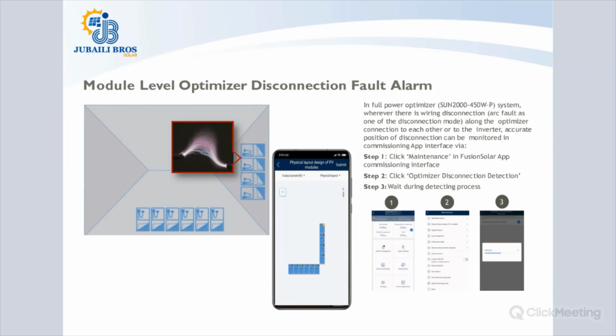Now, it will not be able to pinpoint to you which module is actually at fault, but with PV optimizers installed, and as I just mentioned in the previous slide, where you're able to monitor the performance of your system at the module level, you are able to pinpoint at the module level which particular module has the arc, and you are easily able to fix it. This is something that is amazing.